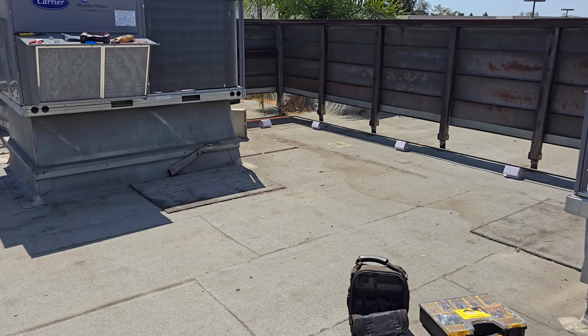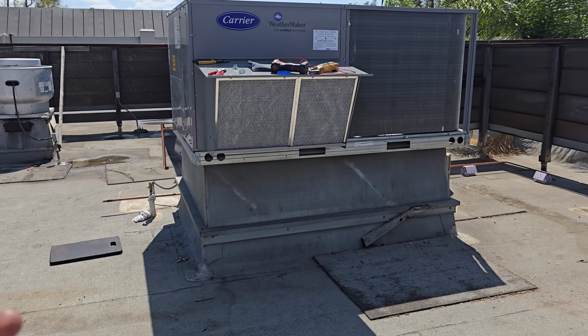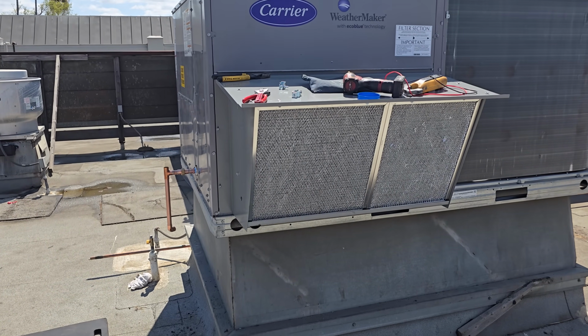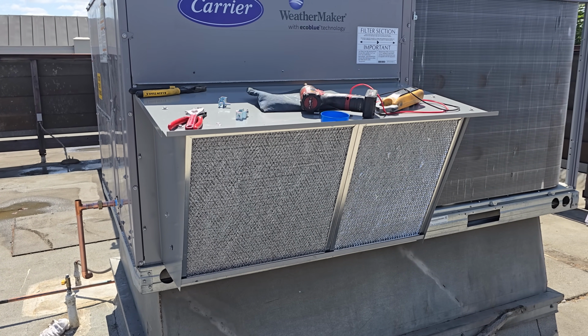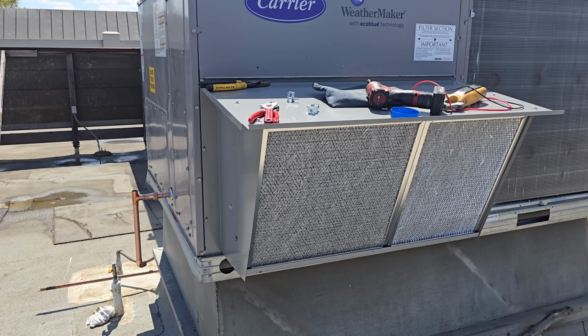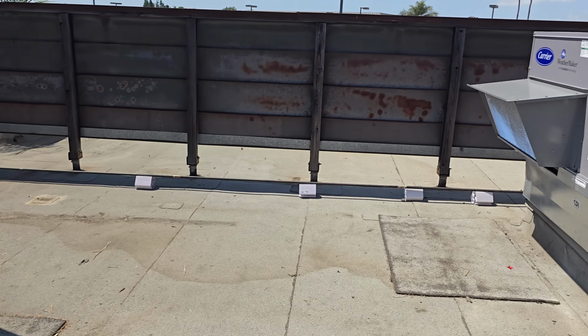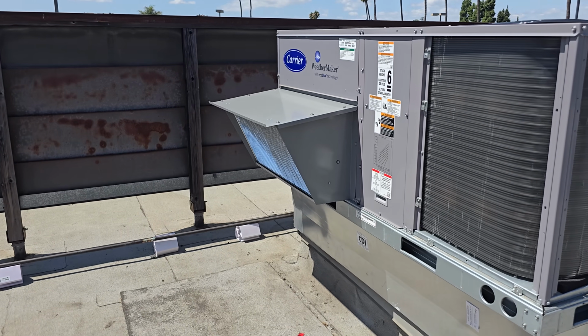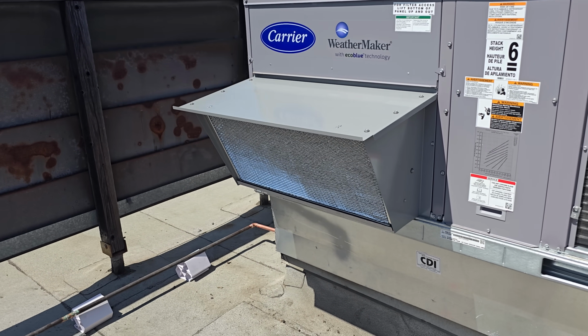As far as the outside air dampers, we did not hook up the economizers right now. We just manually open the dampers because they have a massively negative air pressure in this building, so we have to open these. So I just manually opened them up. I need to manually open this one still. And then we will come back and program the economizers and do all that later.